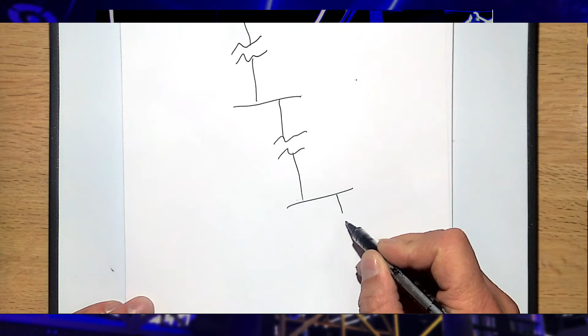So James Smith is asking, where do you place the capacitors? Next to the harmonic device, at the bus, etc. So what about placement of the capacitors? If you make them into a harmonic filter, let me switch over here a second. Let's say I have another transformer, and I have my drives or whatever my harmonic loads are that are producing harmonics. If I put a capacitor here, or if I put a capacitor here, I'm going to have resonance.